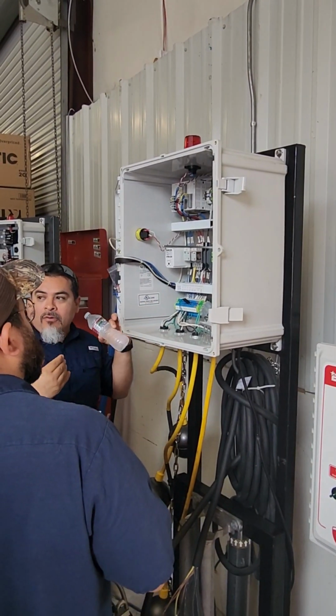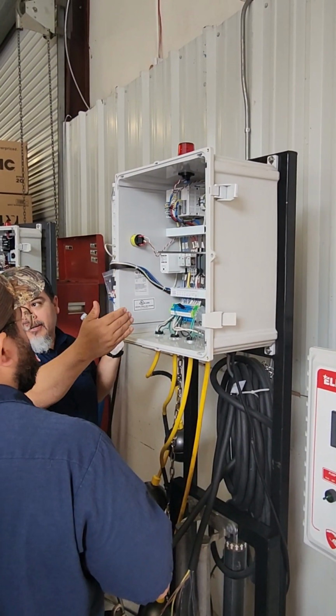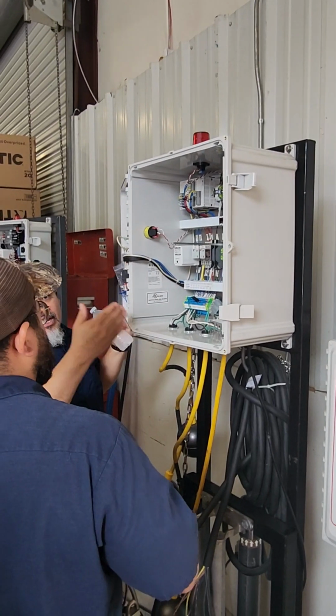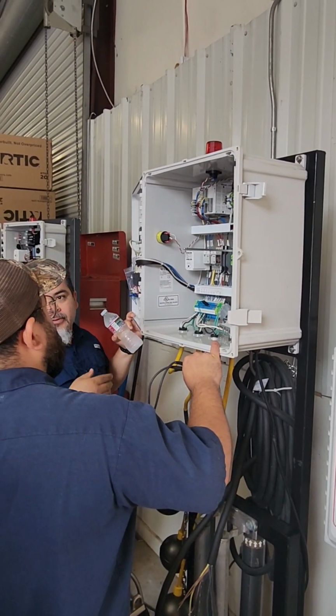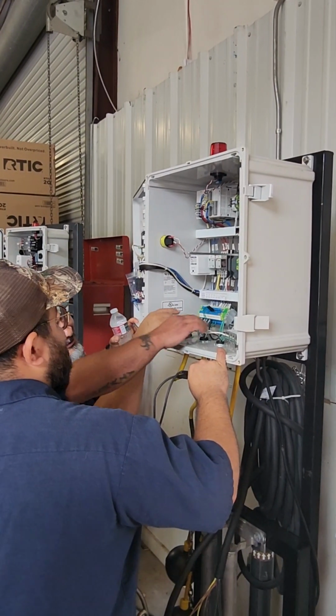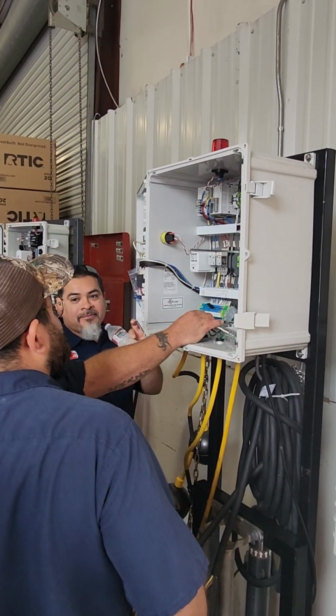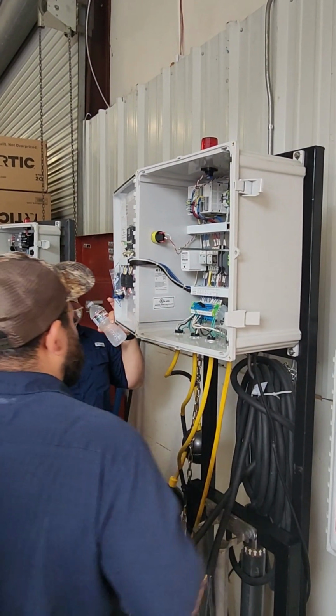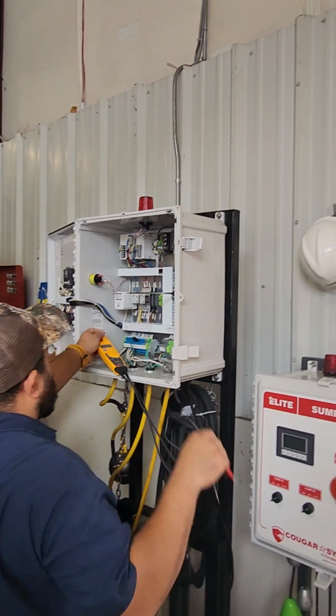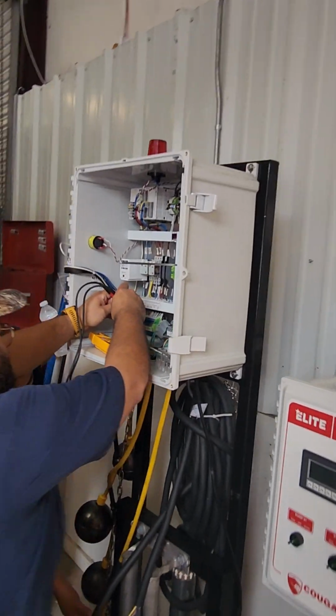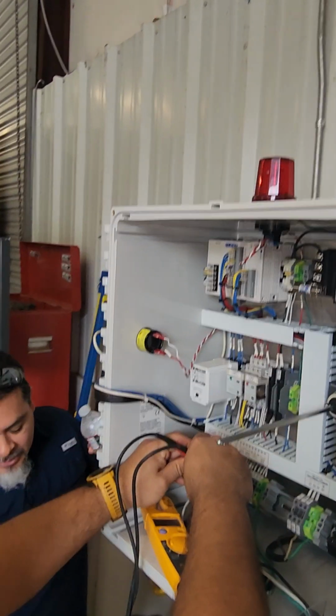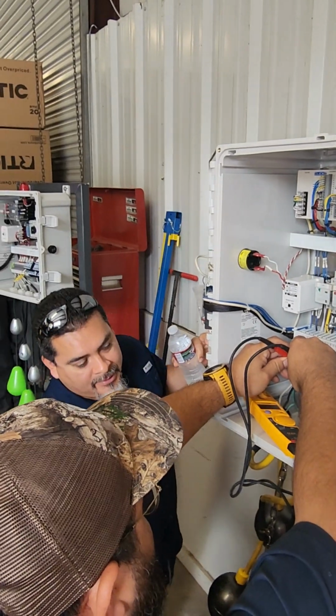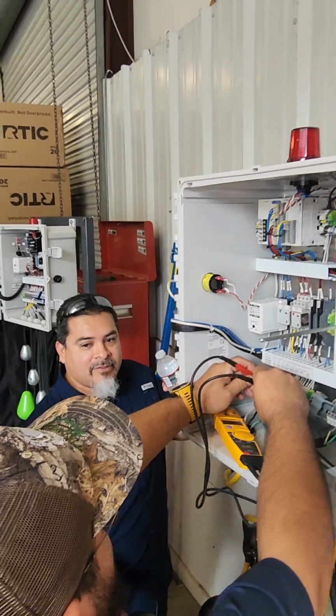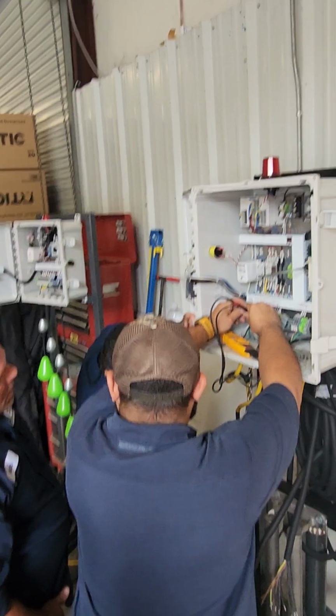A lot of old systems go from left to right, off, on. We do the opposite. We like to be different. Yeah. Okay. So your off will be what terminal? Your off is going to be 7 and 8. All right. So you would check in between that. Okay, so then you flip it, activate it. That way, if you don't have the screen, you'll know which float is what.